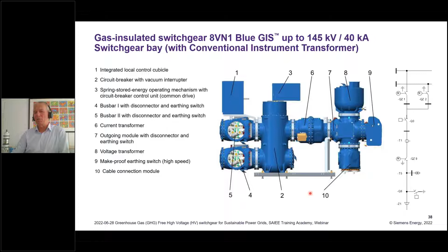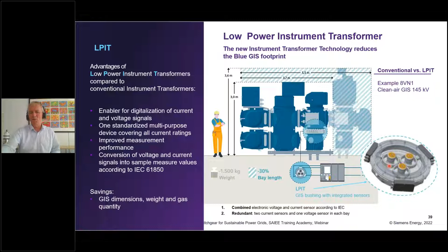What's important is that you can substitute the very big current and voltage transformers by a new technology called low power instrument transformers. And the low power instrument transformers integrate into that cast resin bushing, which you always have in here all over the place. You can integrate the measurement of current and voltage into the cast resin. That makes the whole setup a lot more compact. You see here the space saving indicated by that area by using that so-called low power instrument transformer instead of the conventional power transformers.